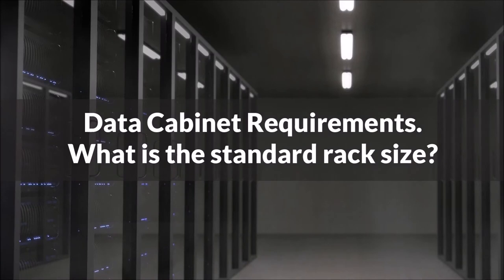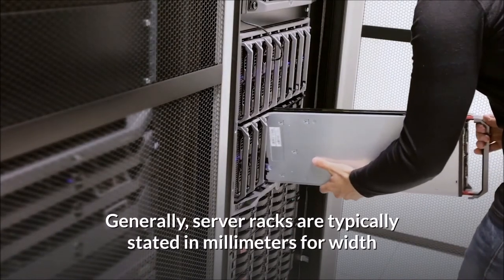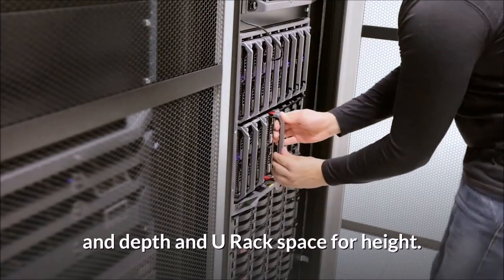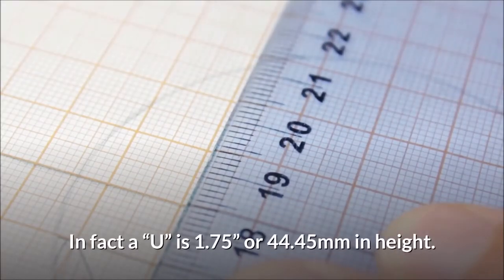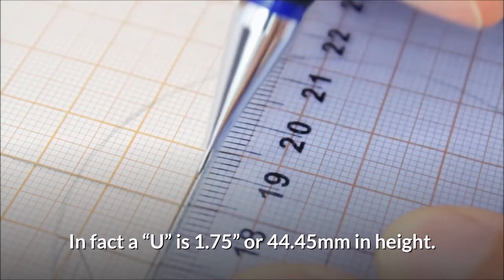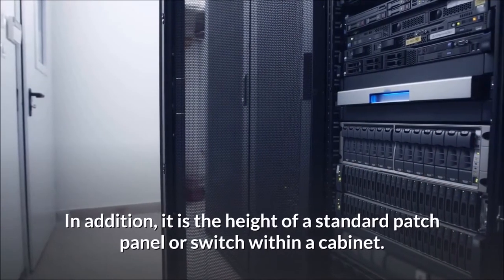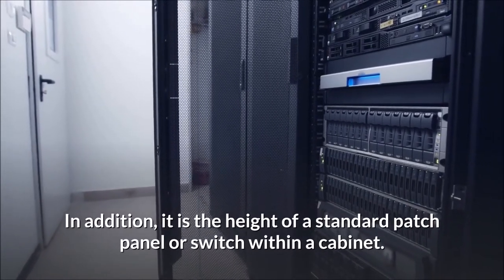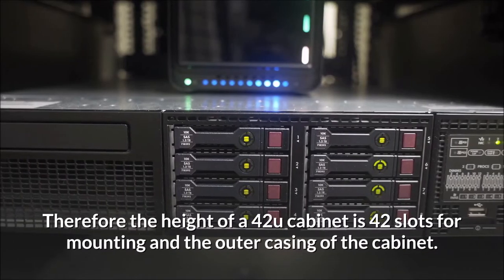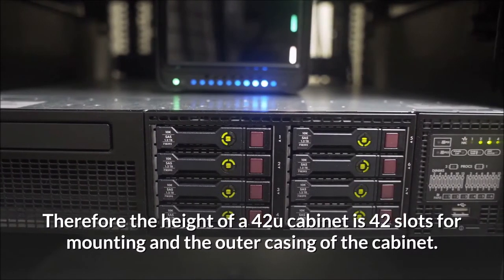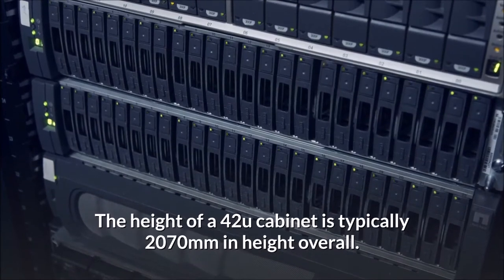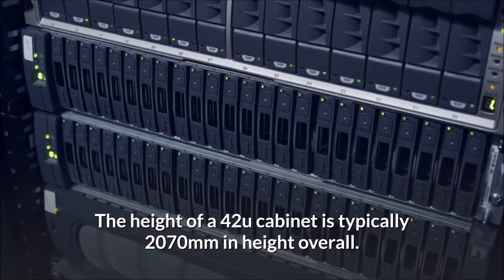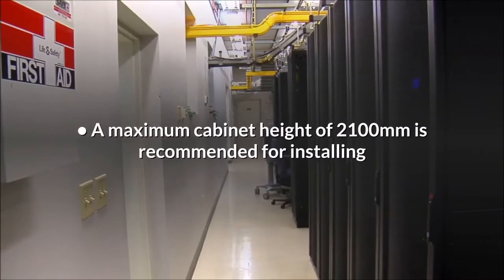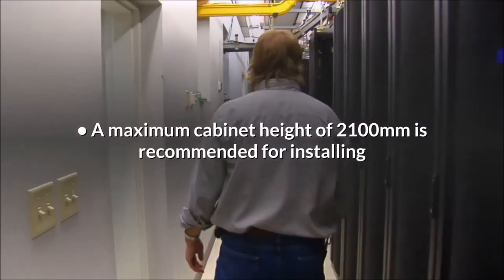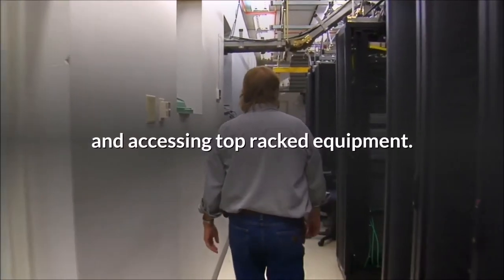Data cabinet requirements. What is the standard rack size? Generally, server racks are typically stated in millimeters for width and depth and U rack space for height. In fact, a U is 1.75 inches or 44.45 millimeters in height. In addition, it is the height of a standard patch panel or switch within a cabinet. Therefore, the height of a 42U cabinet is 42 slots for mounting and the outer casing of the cabinet. The height of a 42U cabinet is typically 2070 mm overall. A maximum cabinet height of 2100 mm is recommended for installing and accessing top racked equipment.